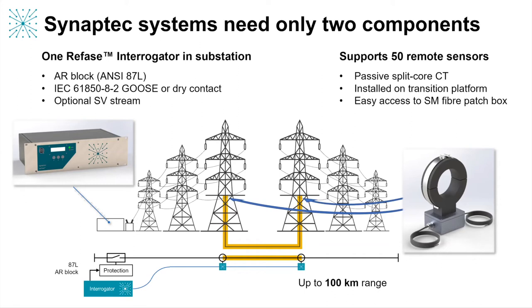The second device is a passive current sensor. We would deploy one of these on each phase at each transition point to enable complete differential protection. Each one of these sensors consists of an industry standard split core current transformer — a CT — the secondary of which is then integrated with Synaptec's unique passive optical measurement technology. The installation requires only mounting of the CT about the cable at the transition platform and standard single mode fiber splicing — both processes very familiar to installers in this sector.